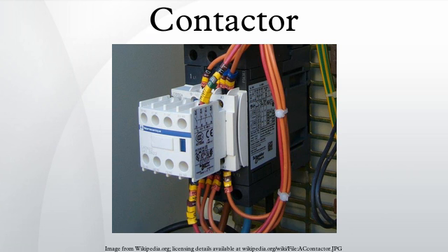For example, a properly applied contactor will have a lifespan of 10,000 to 100,000 operations when run under power, which is significantly less than the mechanical life of the same device, which can be in excess of 20 million operations. Most motor control contactors at low voltages are air brake contactors. Air at atmospheric pressure surrounds the contacts and extinguishes the arc when interrupting the circuit.